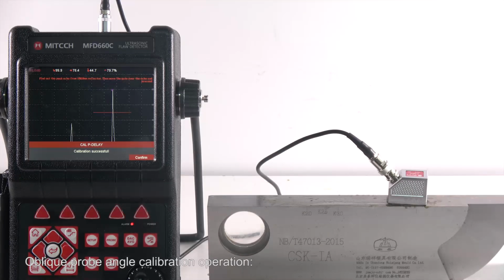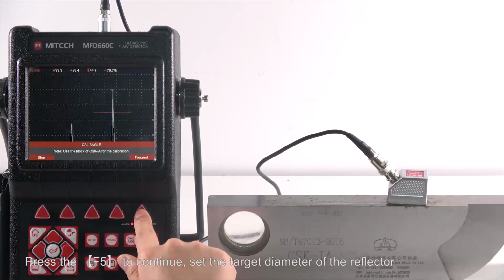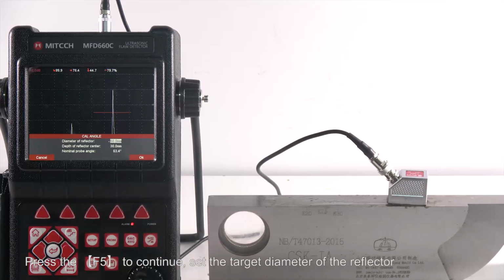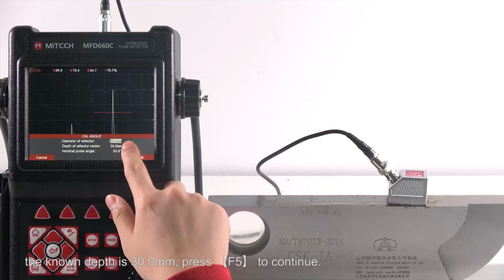Oblique probe angle calibration operation. Press F5 to continue. Set the target diameter of the reflector and the center depth of CSK1A. The diameter is 50 mm. The depth is 30 mm. Press F5 to continue.